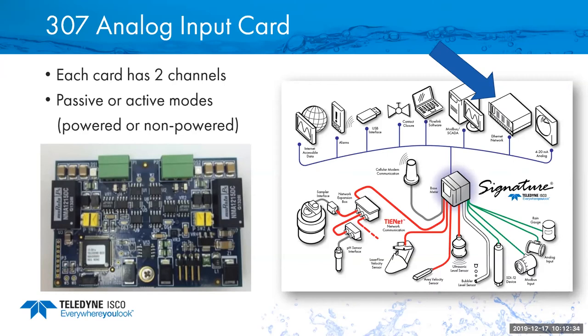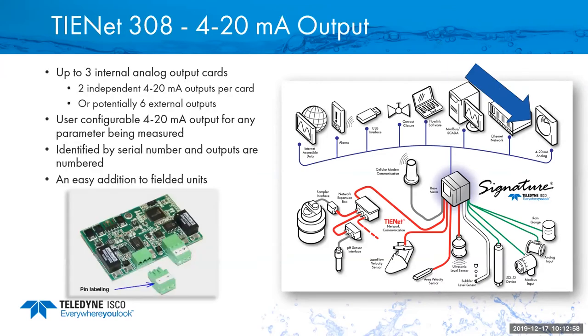We can behave in both a passive or active mode, meaning that for the sensor, we could have an analog pressure sensor that you could connect up that we're actively powering, or it's a powered sensor or powered 4 to 20 signal from a 4 to 20 loop that could be brought into the signature as well. Just a quick switch on the board allows us to set either active or passive.